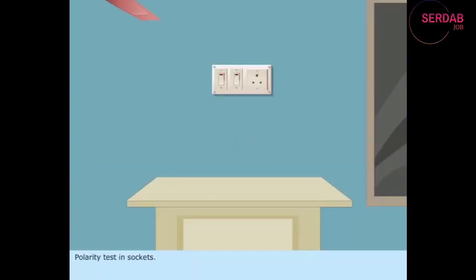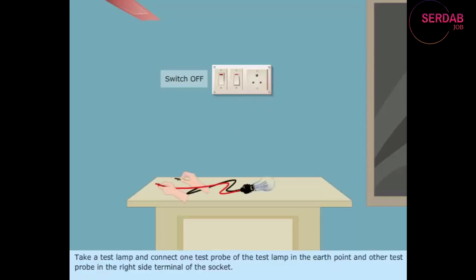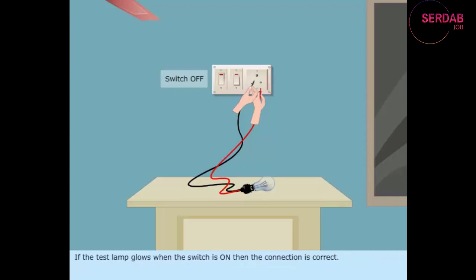Polarity test in sockets. As per IE rules, the right side of the socket point is phase, and left side is neutral. To conduct this test, first keep the socket switch in off position. Take a test lamp and connect one test probe of the test lamp in the earth point and other test probe in the right side terminal of the socket. If the test lamp glows when the switch is on, then the connection is correct. Otherwise, correct the connection.